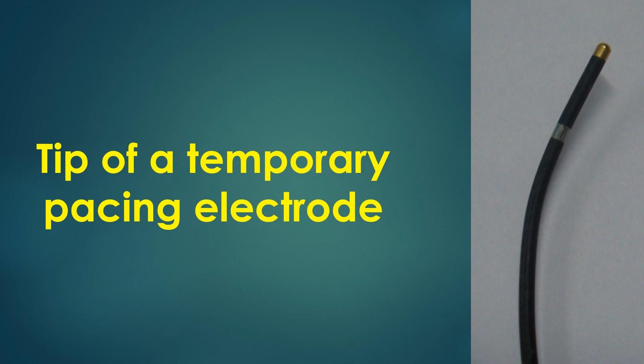Threshold is the minimum voltage needed for capturing the chamber paced. Here the tip has a golden color and the proximal ring electrode has a silver color. But this is not a universal color code. Some temporary pacing electrodes have the same color for both electrodes.